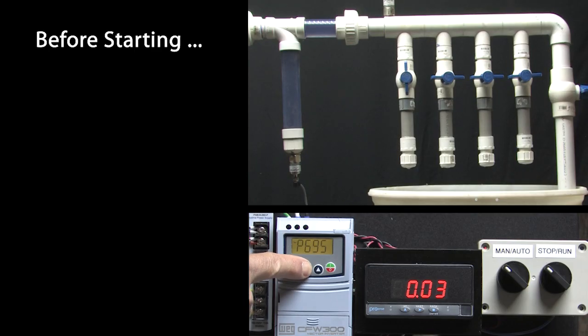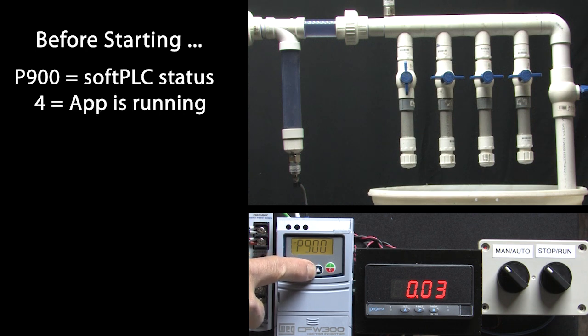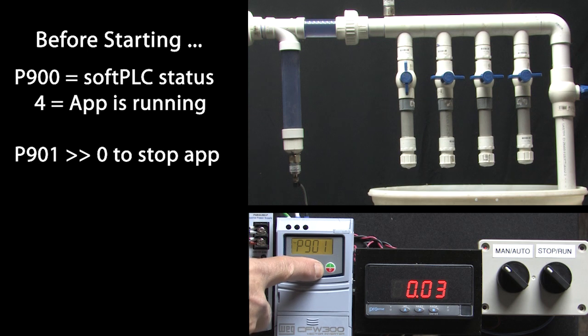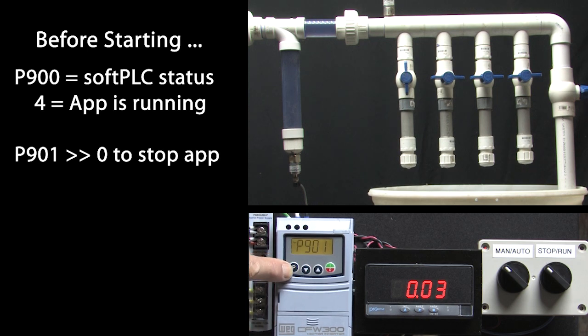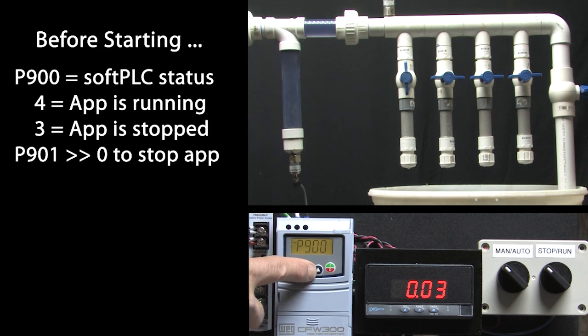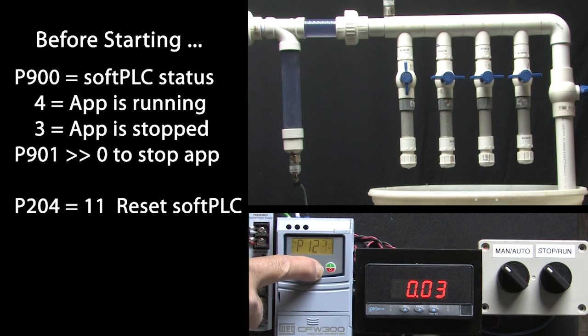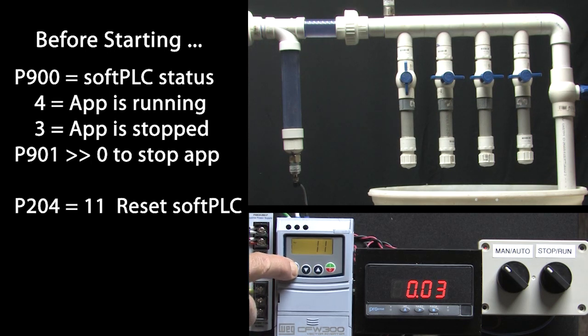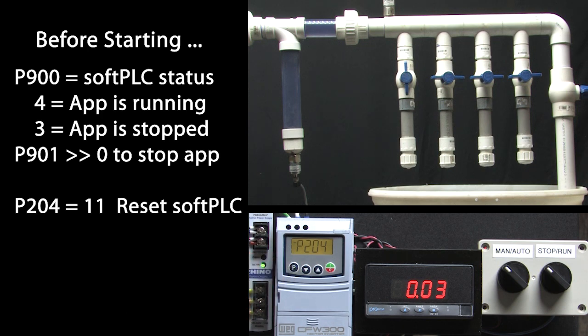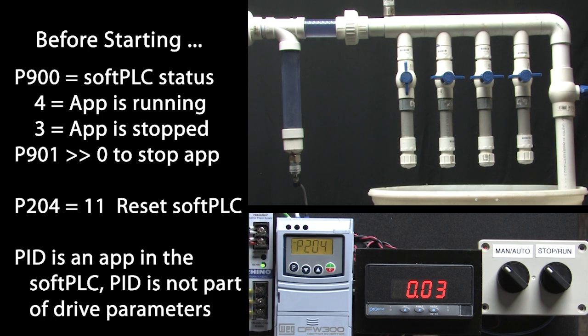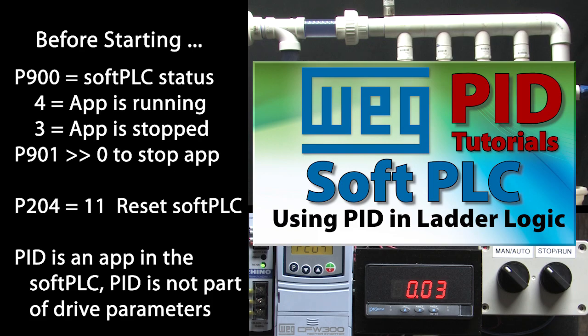Before starting, go to parameter 900. A 4 says an application is currently running. So I'll go to parameter 901 and set it to a 0 to disable the soft PLC. Go back to parameter 900 and we see a 3 which tells us the application is not running. Now we can go to parameter 204 and set it to an 11 to reset all of the soft PLC parameters. The default soft PLC app is the PID function the drive uses. PID isn't actually in the drive, it's in the soft PLC. We'll talk more about that in the soft PLC PID video.